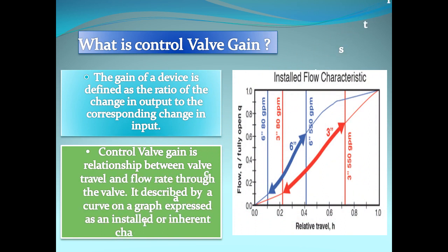What is control valve gain? The gain of a device is defined as the ratio of change in output to the corresponding change in input. Control valve gain is the relationship between valve travel and flow rate through the valve. It is described by a curve on a graph expressed as an installed or inherent characteristic.